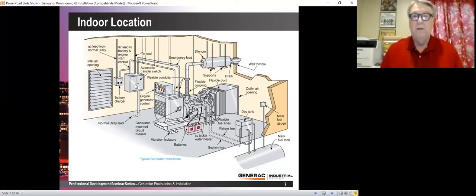Now over here is an automatic transfer switch, and then you've got your battery charger. I think this is not the best place for a battery charger over here. Not saying you couldn't use it, but battery chargers are very sophisticated these days, and you really don't want the voltage drop between that battery charger and the battery. And so typically we're going to mount battery chargers on the generator. Not a code issue, but just something that I would do if it were me.